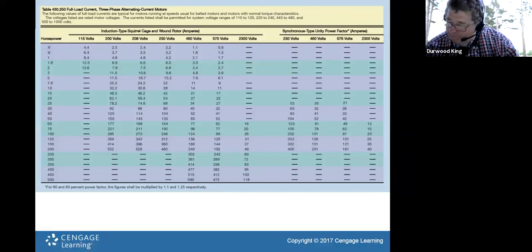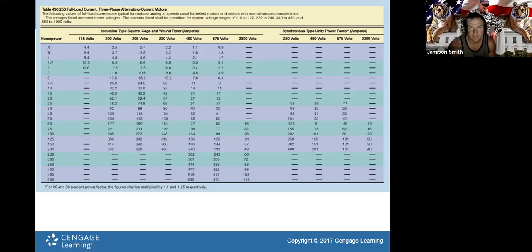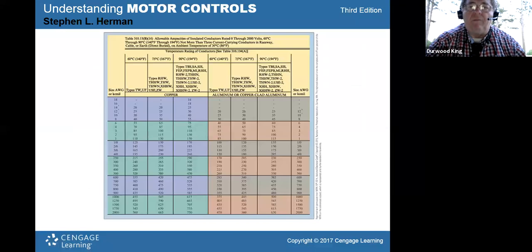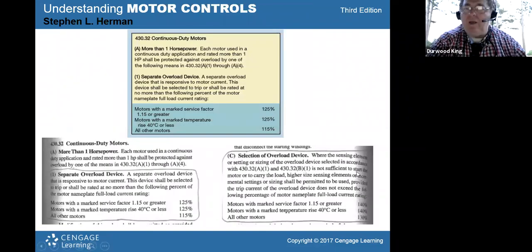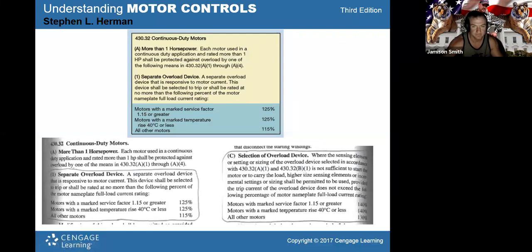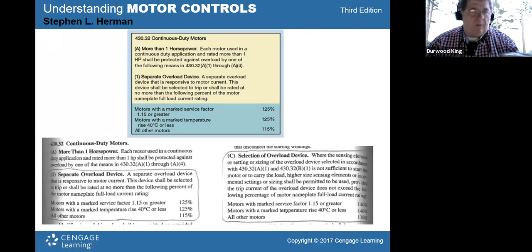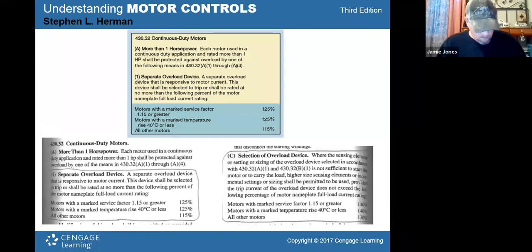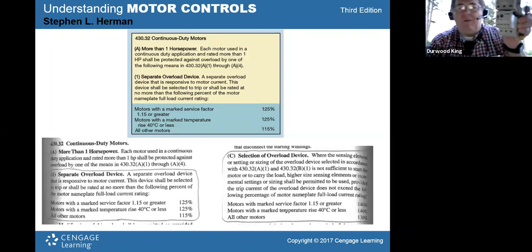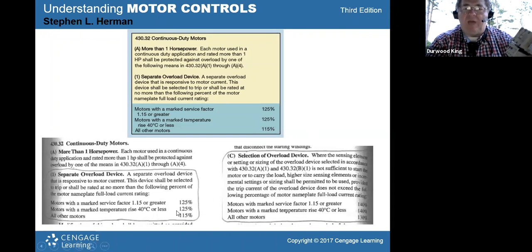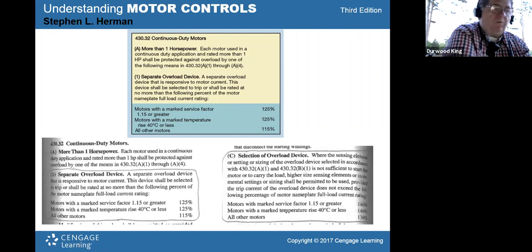So 414, you take that original number off of the chart, and you multiply it by 1.4. That's 140%. So 414 amps times 1.4 instead of 1.25. So it'd be 580 roughly. 580 amps. So listen, that would be your worst case setting on the overload there. You can set the overload at 140% if 125% is not enough, for loads that are heavy loads on startup, where it takes them a long time to ever start up. You can do that. Okay.